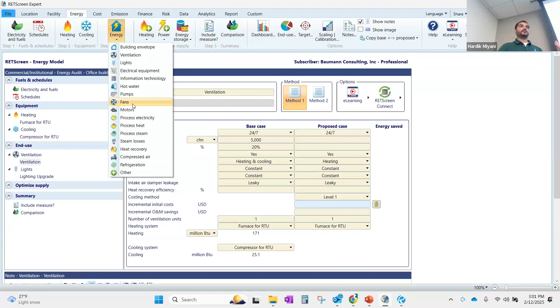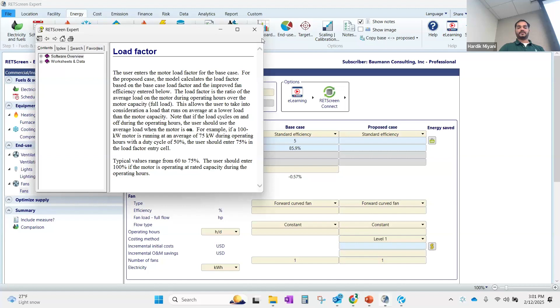It is a 5 HP. No need for manufacturer and model number. Load factor. Now they haven't given anything about the load factor, so I don't know what to consider. So I will select RETScreen typical values, right? As per RETScreen, the typical range is 60 to 75%. The user should enter 100% if the motor is operating at rated capacity during the operating hours. I will assume it is not operating at rated capacity. I will assume a 65% load factor.